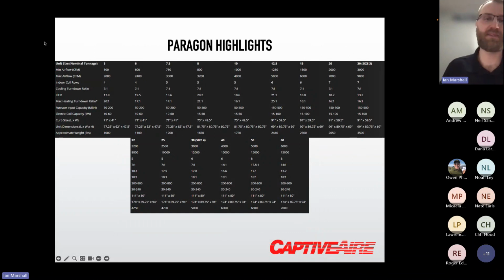To go into some of the specifics on the unit sizing, this is a table showing our different tonnages. We range from 5 tons up to 60 tons, in 4 different cabinet sizes. The airflows listed here are general airflows that blowers within those cabinets can hit. But again, these selections are very specific to an application and to a location, depending on ASHRAE weather data and that kind of stuff. So we're not necessarily always going to be running 3,000 CFM through a 7.5 ton unit. It's location based.